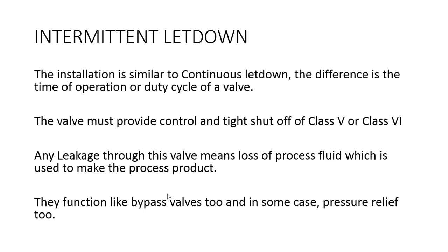They function like a bypass valve, and in some cases they can work as a pressure relief valve too. The valves are designed to bypass the entire process or a part of the process during startup, shutdown or emergency conditions. The important points which we need to consider in this case are the stroke speed and the shut off. Usually, when this valve acts in a safety function, the speed must be within 1 to 5 seconds to close, because its function is to protect the personnel, equipment or process output.